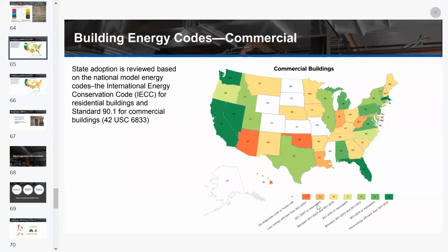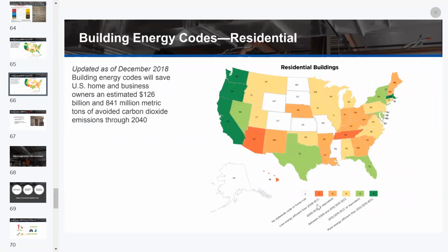Next slide. Building energy codes, commercial: safety codes, energy codes, and standards are all developed independently, and the most recent edition of a code or standard, as we all know here in Texas and Oklahoma, may not have been adopted by a local jurisdiction. HVAC designers need to know which code compliance obligations affect their designs. Where is this building going? They need to make sure they're following that. Also, if an HVAC designer is going above code, that's obviously a great thing. But if there's a conflict with design intent, then they need to resolve that issue with the local building official.